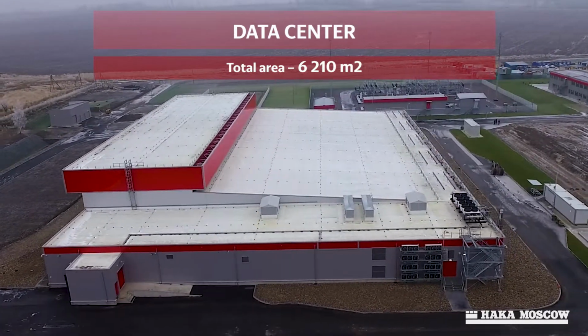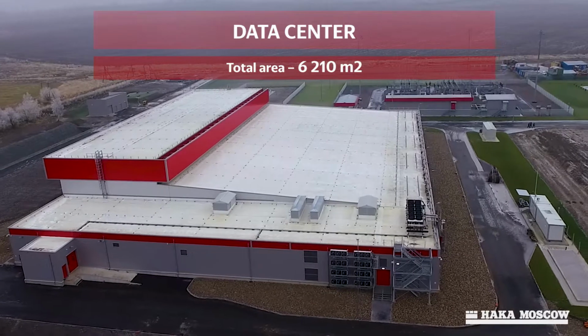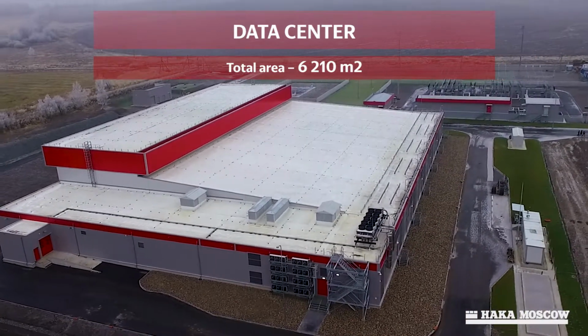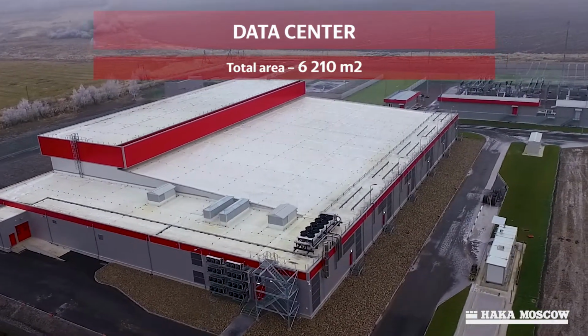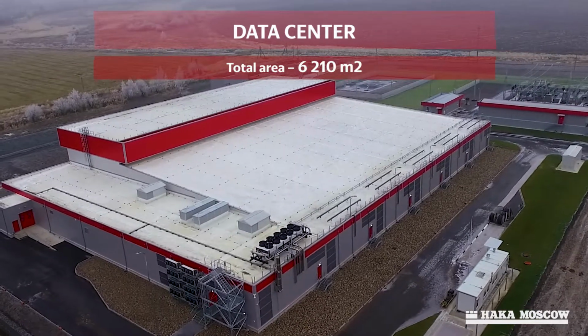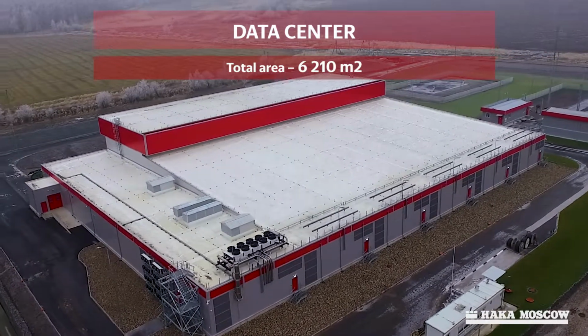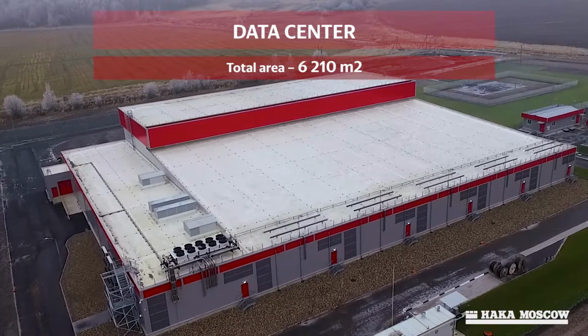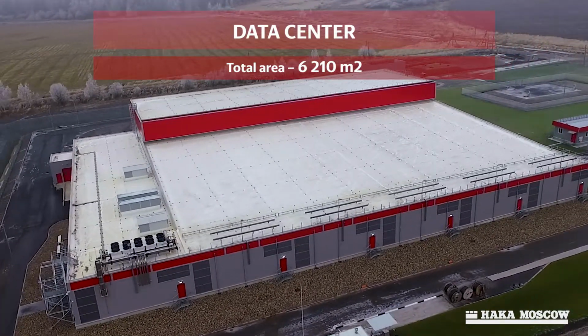This new center for Yandex's data processing and storage is the first such facility in Russia not to have supplementary ambient air cooling for the operation of the technical equipment. Not having to spend energy on such cooling helped the center achieve Russia's most energy-efficient power factors, with power usage effectiveness rated at 1.07 for the already fulfilled module.